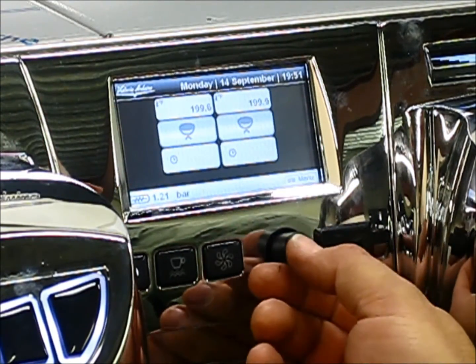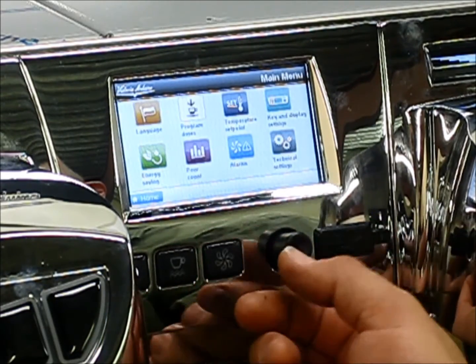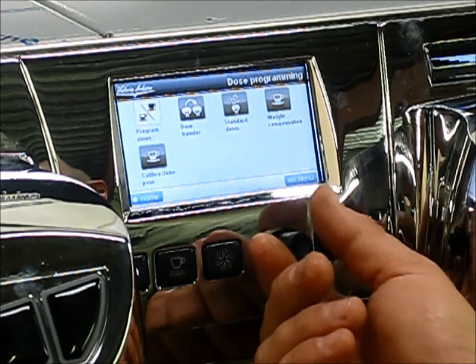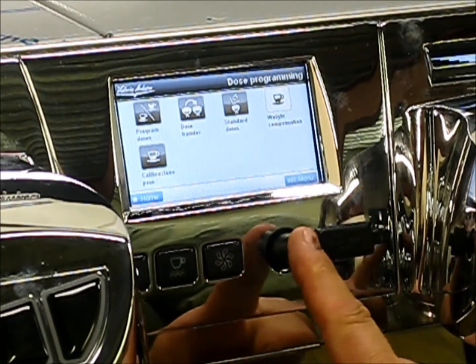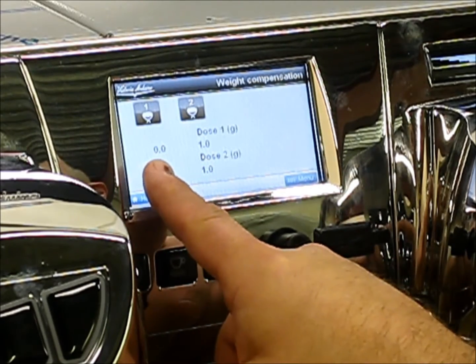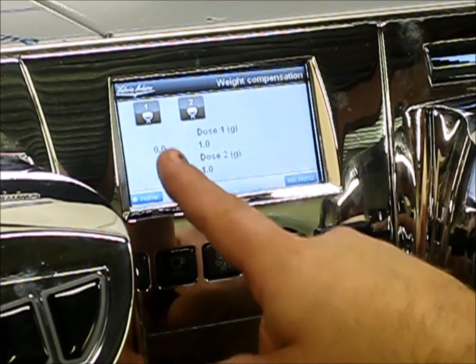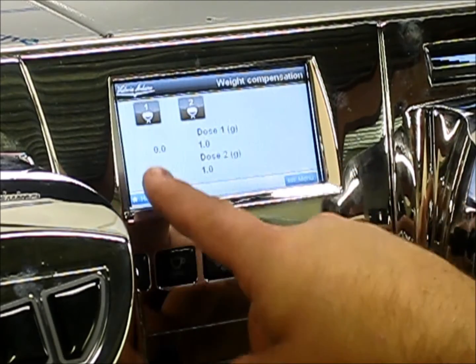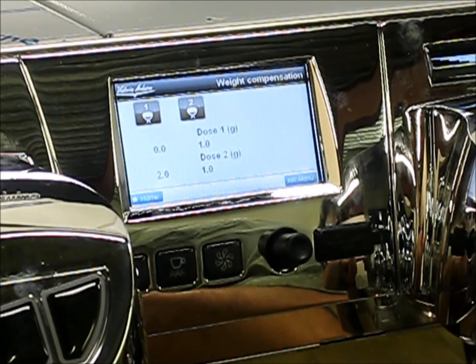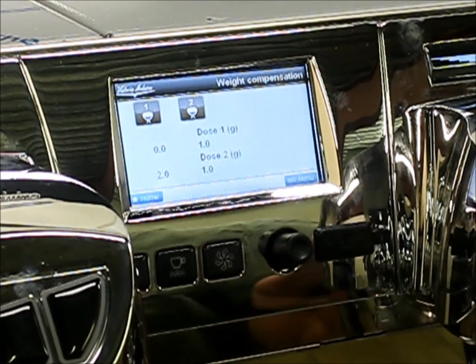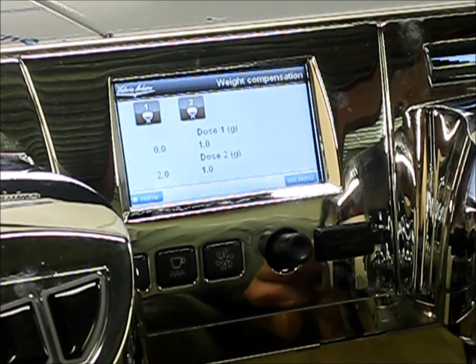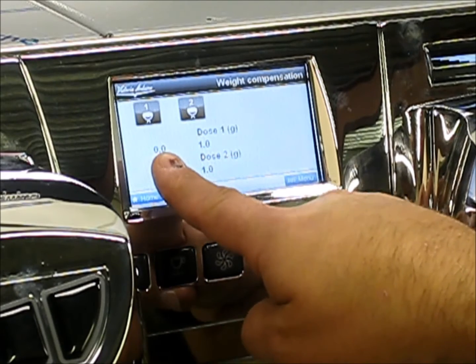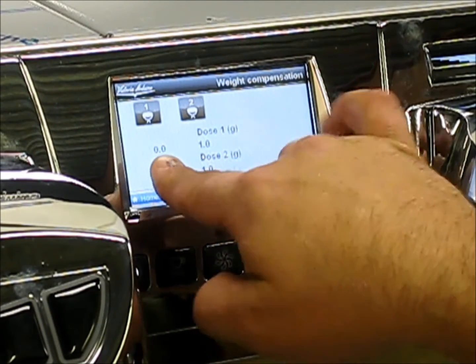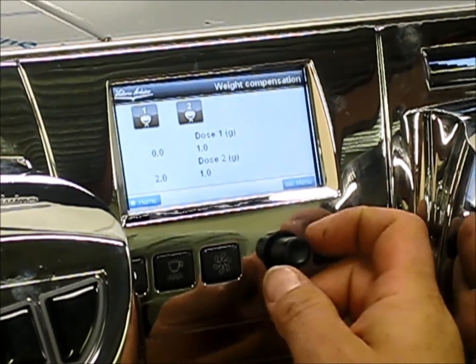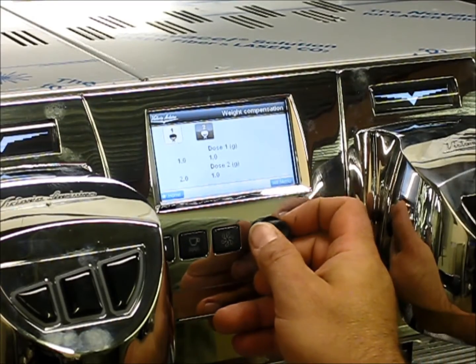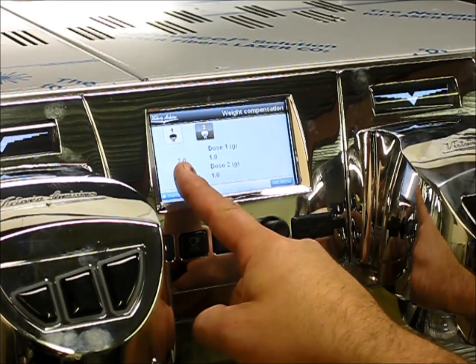To access the compensation page, you'll press Menu. You'll scroll to Program Doses. In Program Doses, you will scroll to Weight Compensation. Pressing the button again, you will now be in a menu that displays Group 1 and Group 2. You'll see four values. For Group 1, there is an offset for button 1 and button 2. Group 2 has the same offsets for button 1 and button 2. In this case, we are going to weight compensate for button 1. We highlight Group 1, and we're going to adjust it by 2 grams.